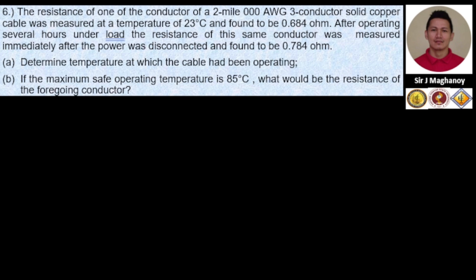Number six: The resistance of one conductor of a two-mile 3-0 AWG solid copper cable was measured at a temperature of 23 degrees Celsius and found to be 0.684 ohms. After operating several hours under load, the resistance of the same conductor was measured immediately after the power was disconnected and found to be 0.784 ohms. Determine: (a) the temperature at which the cable has been operating, and (b) if the maximum safe operating temperature is 85°C, what would be the resistance of the foregoing conductor?